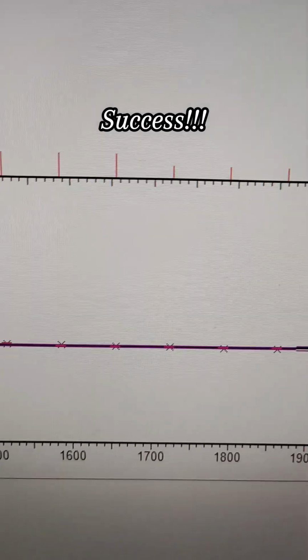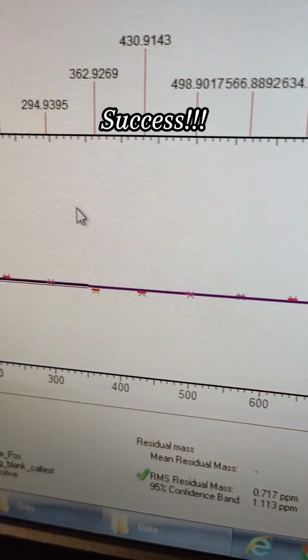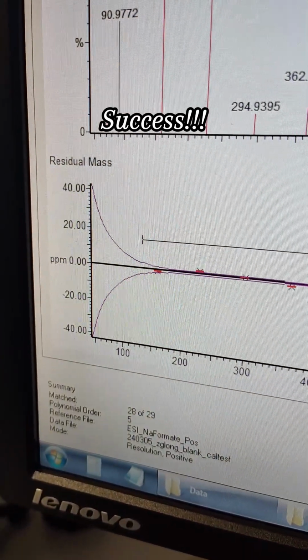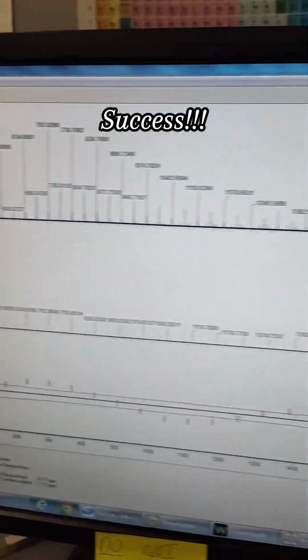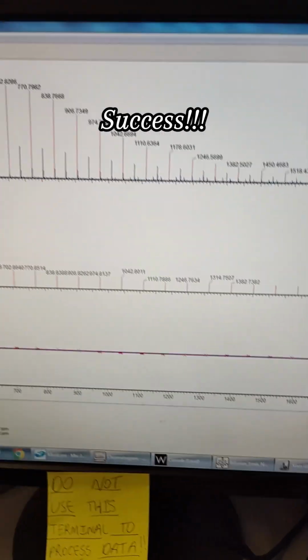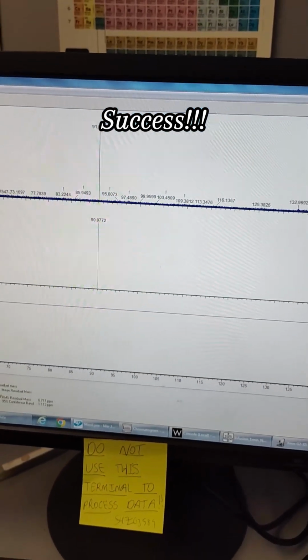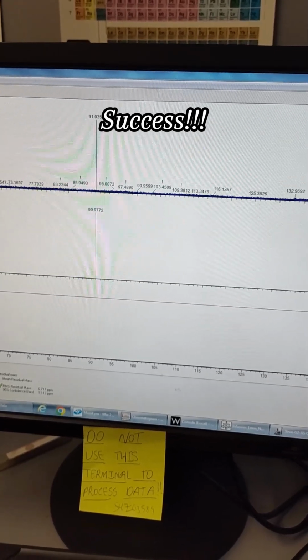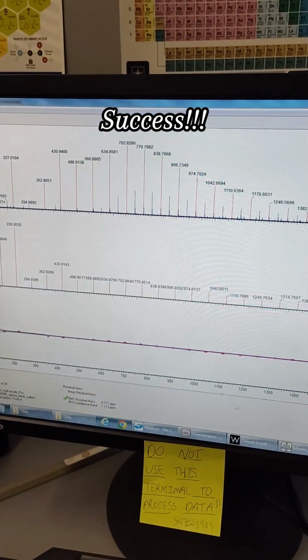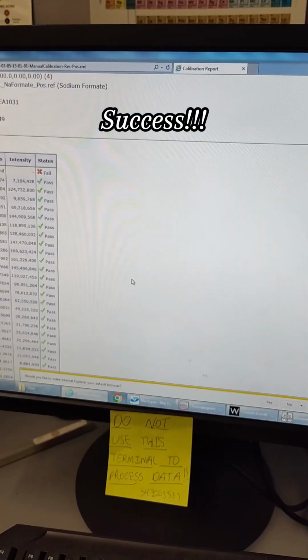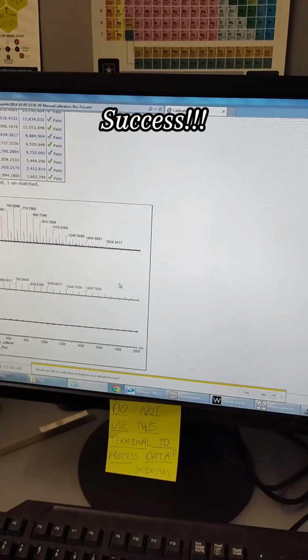You can see we got really good, almost no error across the range except for down low where we're kind of missing the peak, but you can see we're within 1 ppm across the entire range, it looks like. And so this should be a pretty good cal file. So we'll just go ahead and accept this. And now we are all passed, and the instrument should be well calibrated.